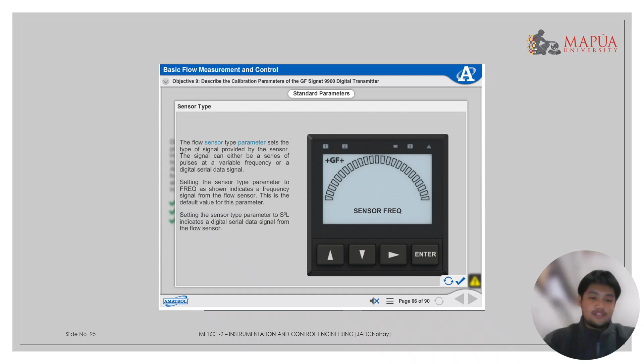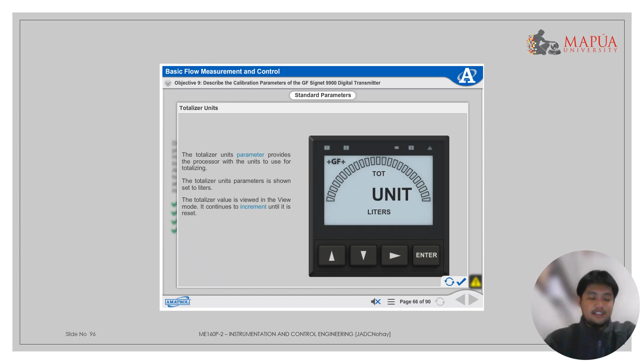The totalizer units parameter provides the processor with the units to use for totalizing. The totalizer units parameter is shown, set to liters. The totalizer value is viewed in the view mode. It continues to increment until it is reset. Now, the additional programmable parameters for the GF Signet 9900.